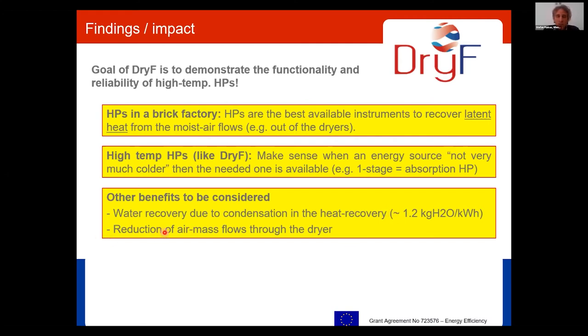And then the second benefit for the operation of our convection dryers is that we reduce the air mass flow through the dryer when we operate with internal heat exchangers. What have we seen so far in Uttendorf? We operated from 120 degrees sink temperature up to 160.